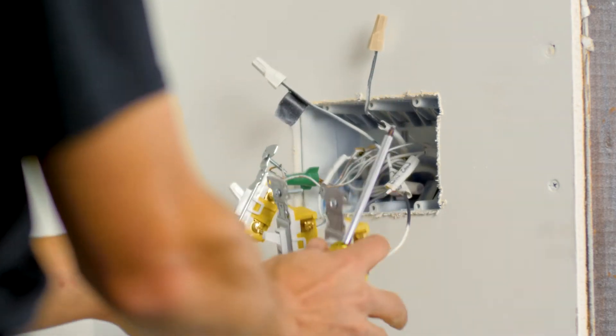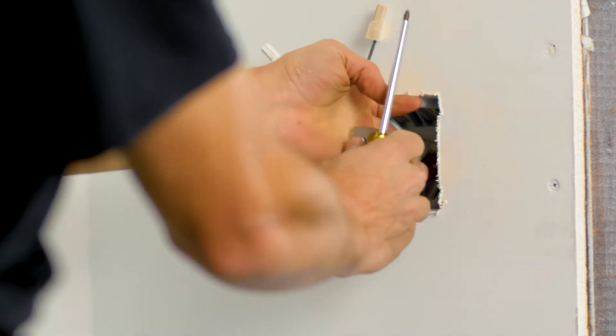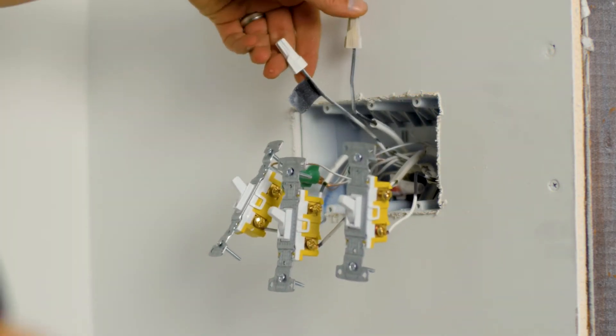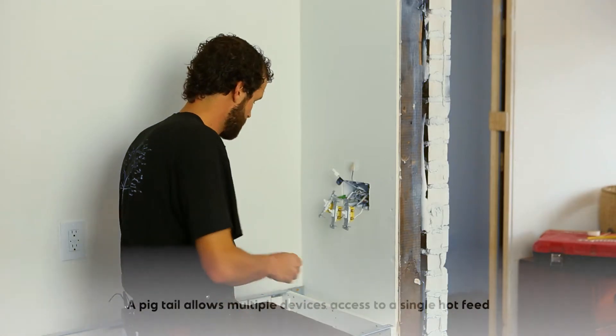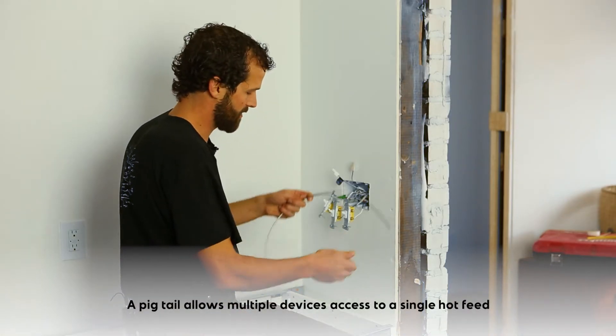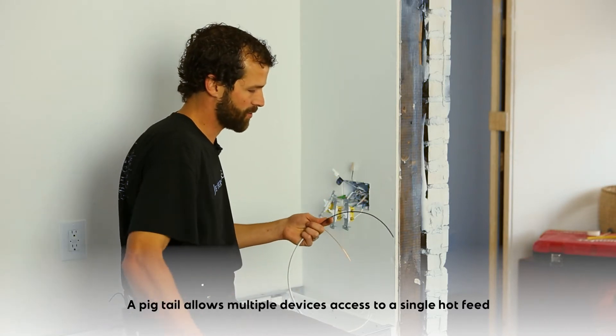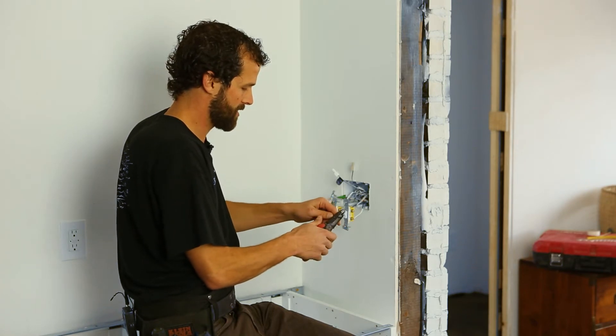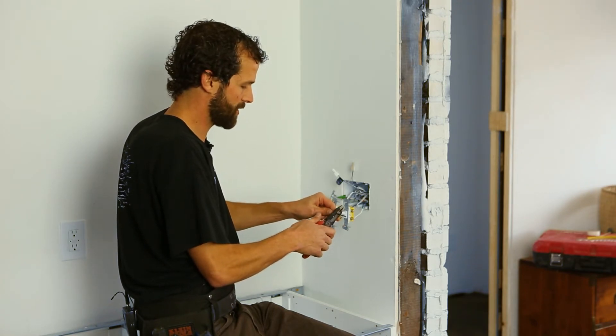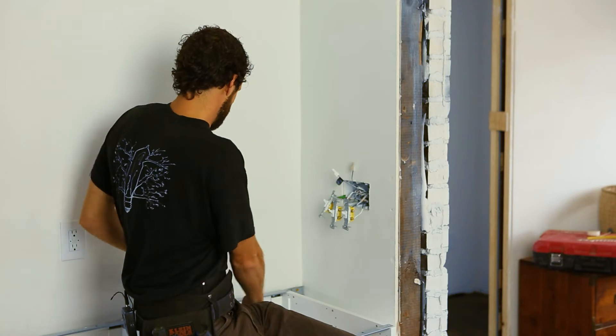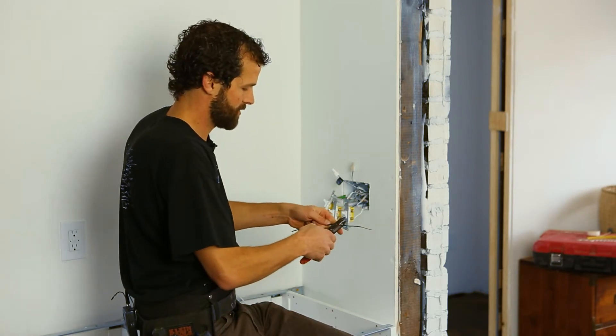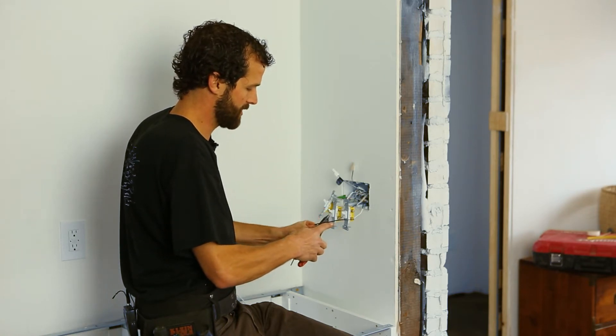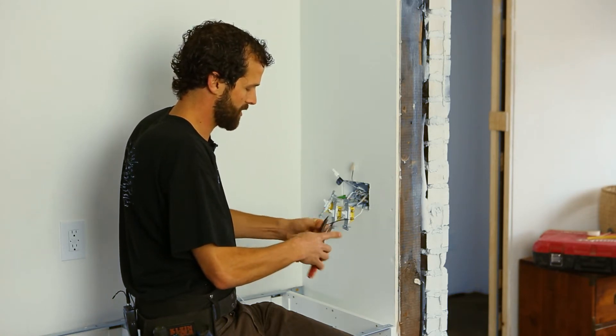So now what I have is all three switch legs have been terminated, and I've got two conductors left, two black conductors in this case that are both hot. What I need is a pigtail. I've got my 14-2 Romex here, and I'm going to cut off about 12 to 14 inches to create that pigtail. I'm going to pre-strip about two inches off the end of the wire. I'm going to come down to about a third of the way.